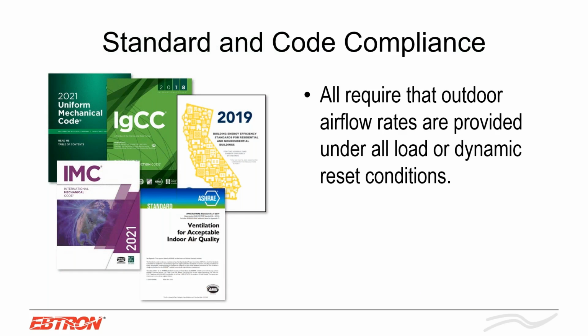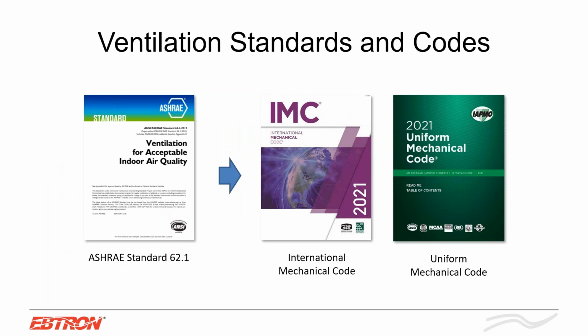Now again, what do these codes and standards say? All require that outdoor airflow rates are provided under dynamic load or dynamic reset conditions. So what is dynamic load or reset conditions? That means as the loads in the space are changing, you need to be able to provide the correct amount of outside air. So as more people are coming into the space, you have to be able to provide the correct amount of ventilation air based on that population in the space.